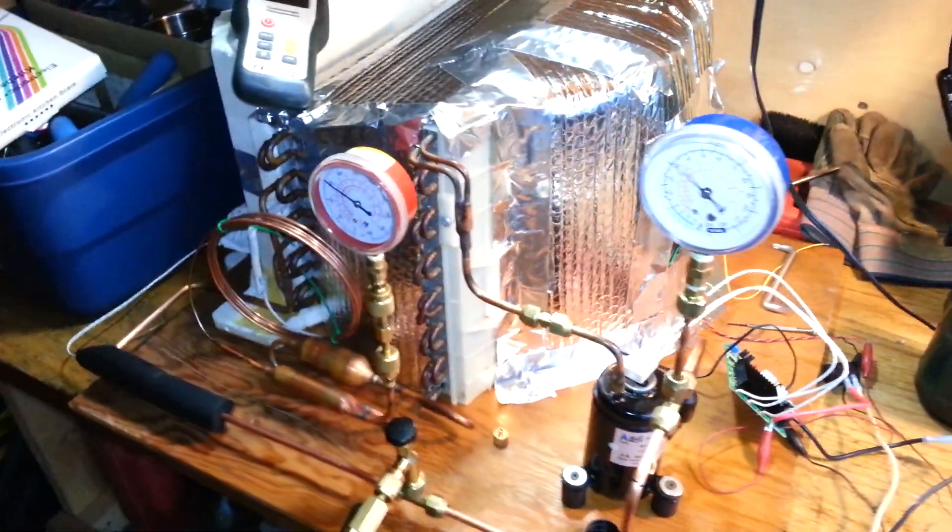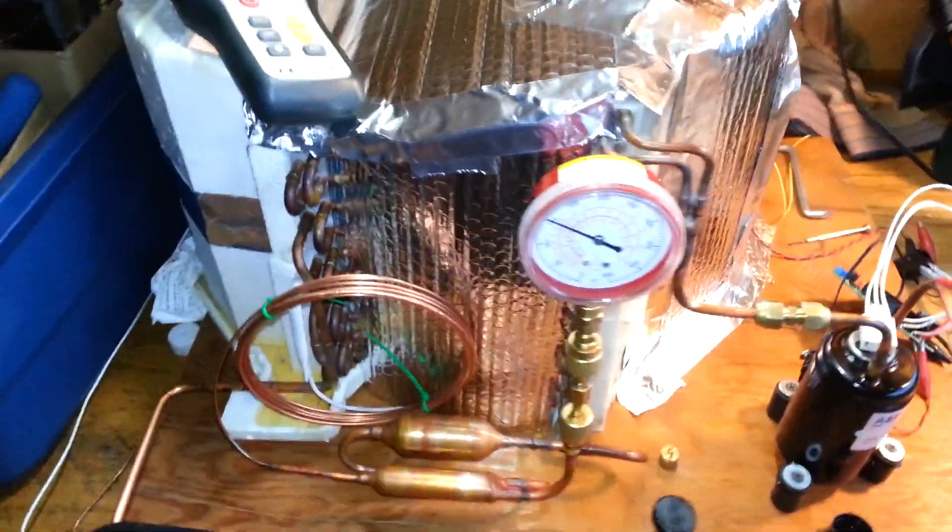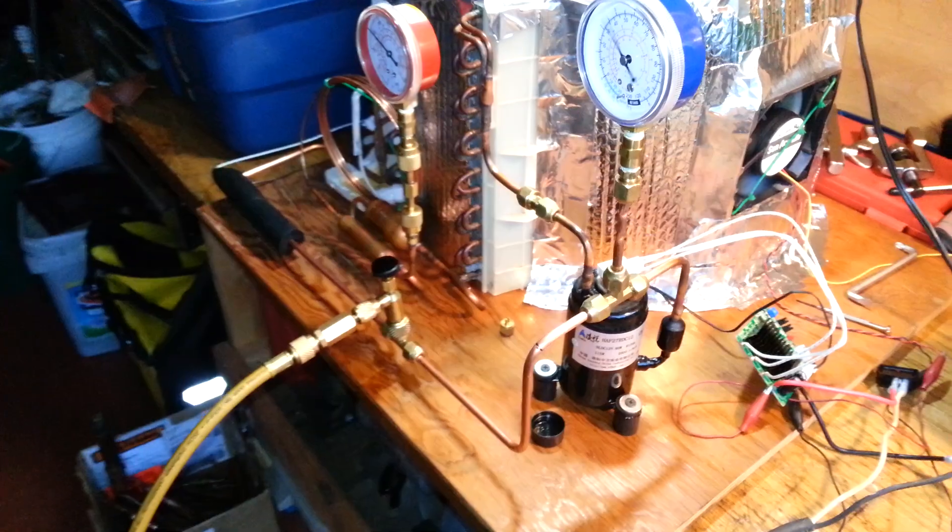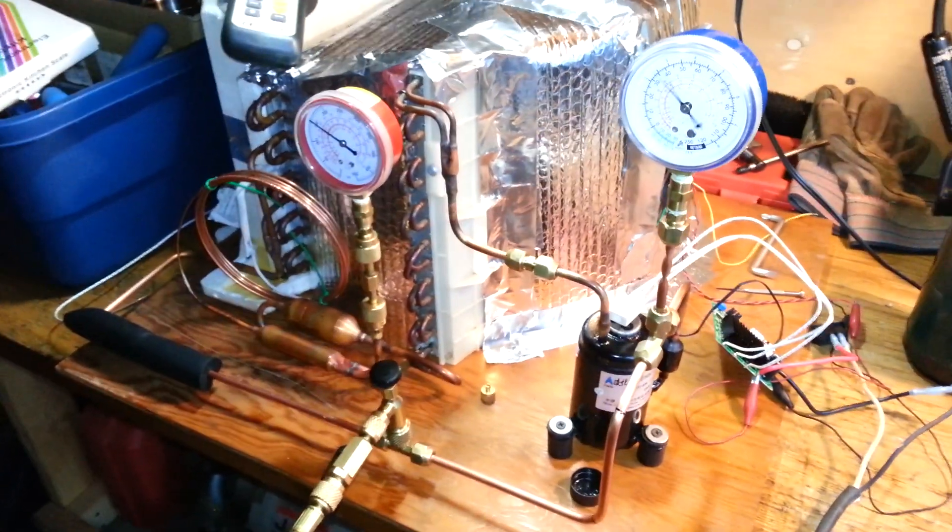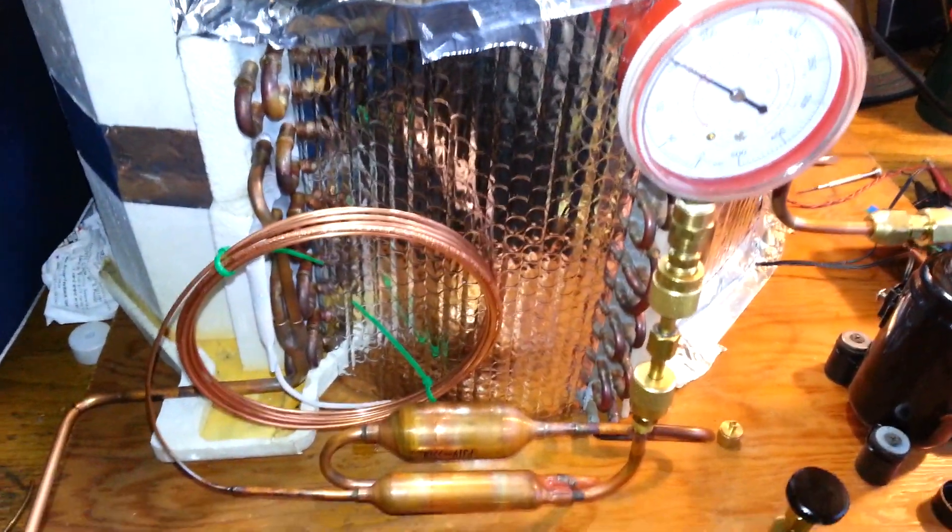Hey, it's Mike here, doing some second tests on a little DC compressor and the dehumidifier arrangement that I have going on here. Now, my preliminary test didn't show that it was going to work out very well with this particular cap tube setup. It's 12 feet of .031 bore cap tubing.